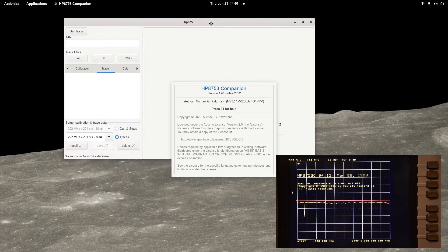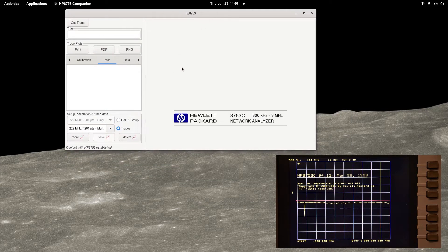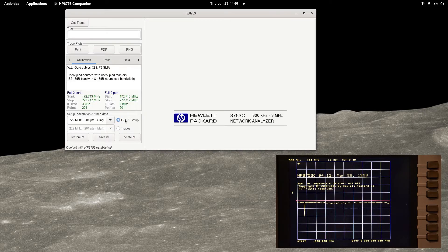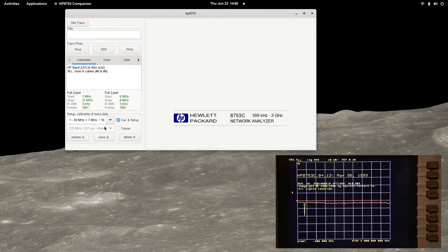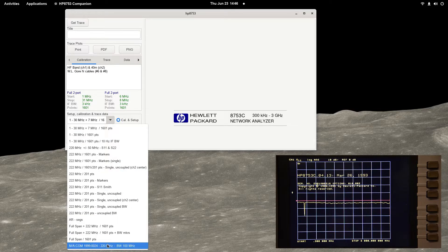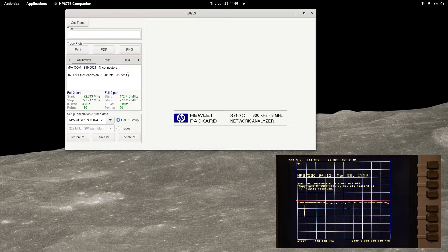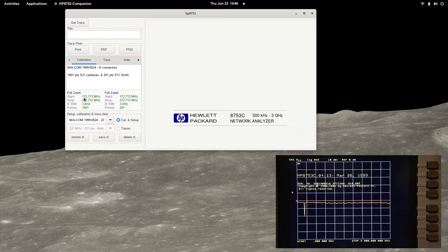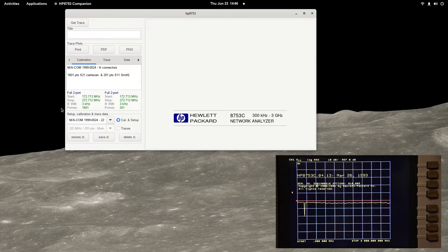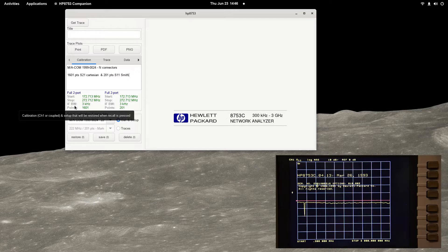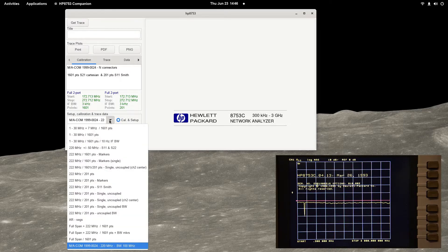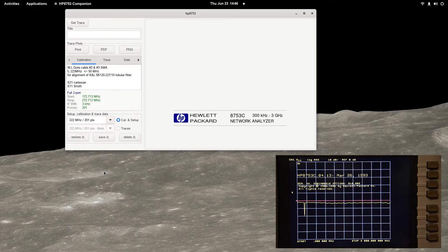One of the most critical and time-consuming setup operations is calibration. The program can quickly restore previously saved calibration and setup profiles. The calibration drop-down control is used to select a saved profile. Source parameters and setup and user added notes are displayed when the selection is made. The chosen setup and calibration data are sent to the analyzer when the restore button is pressed.